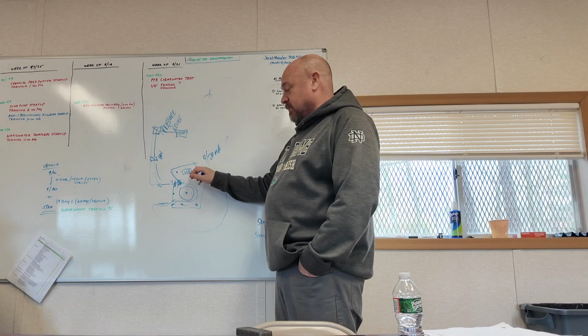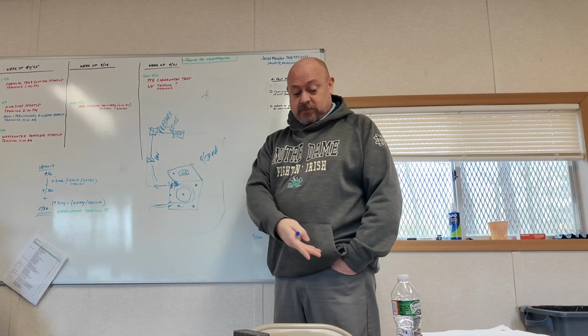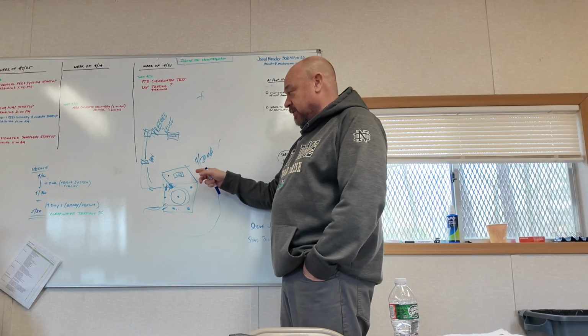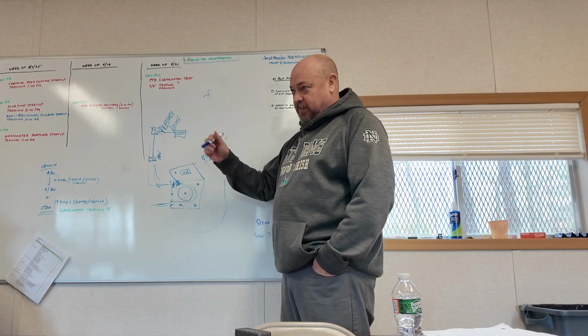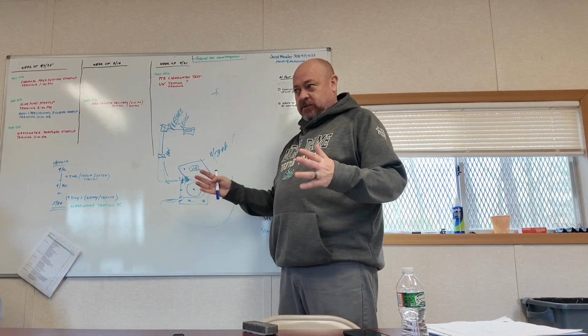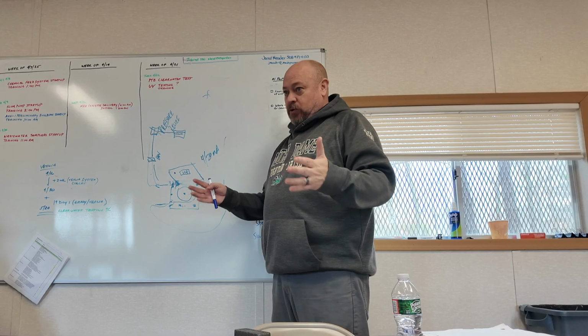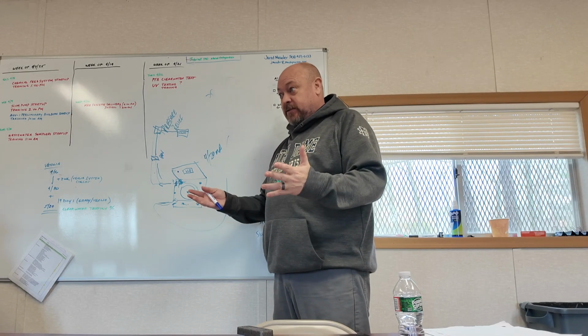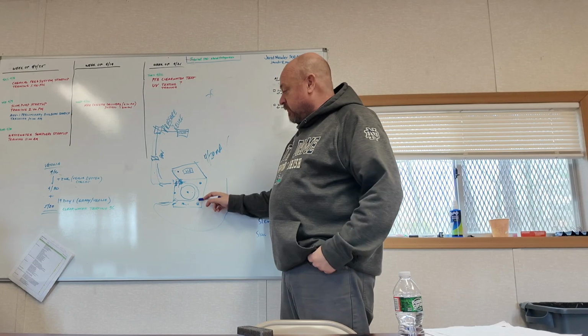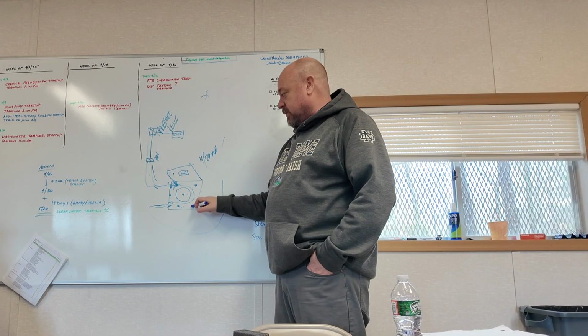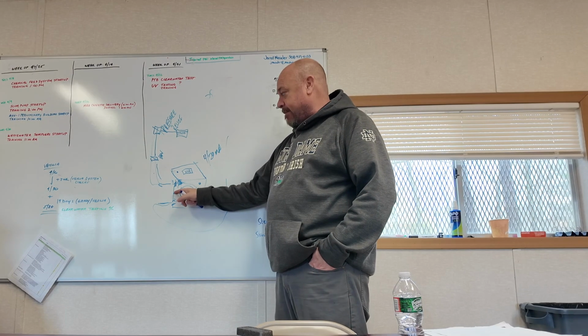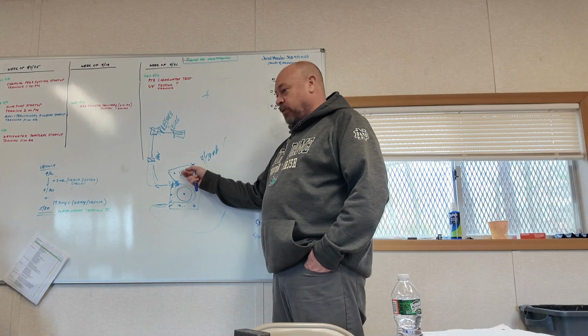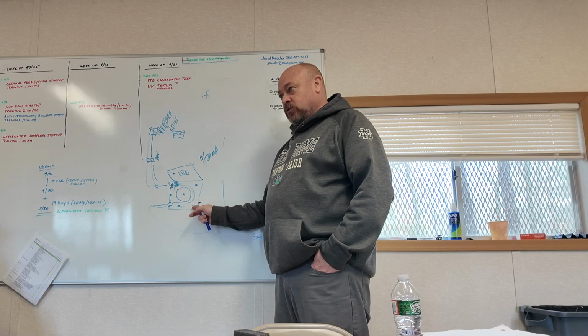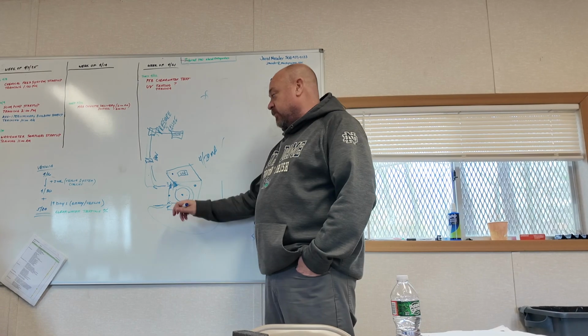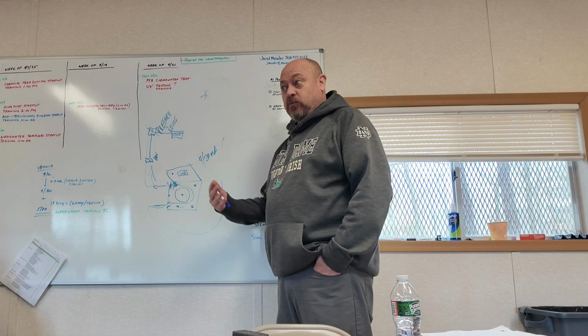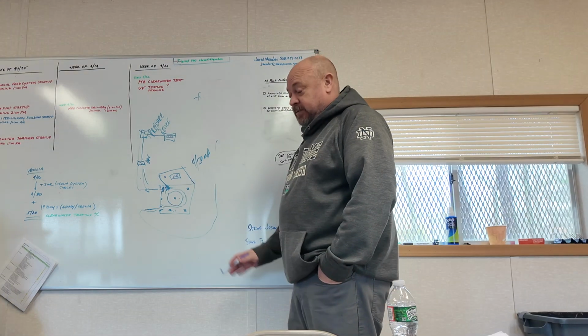So sometimes the display will get funky. It's like your iPhones, a touch issue with the display if you get chemical underneath it. And then also if you're running them at high speeds, some of the bigger ones like the citric acid and your hypo ones, those are 100-gallon-an-hour pumps. If you run those at 100 gallons an hour, that thing really starts to rock and roll. The front cover assembly will start to shake. The bolts, those little thumb screws, will come loose, and that magnet will disengage and it'll go into pump maintenance mode. If you have those issues, just try to tighten down the thumb screws first. And obviously if you've got any type of chemical on that magnet, it won't recognize the magnet back and forth. But other than that, these things are bulletproof.